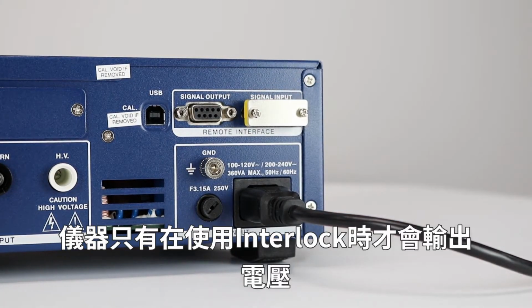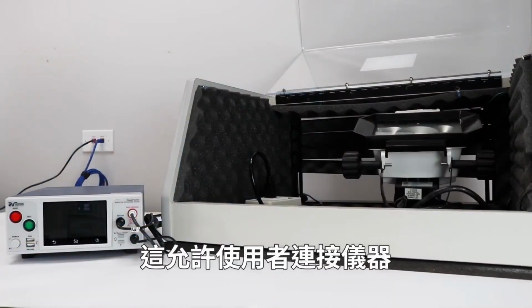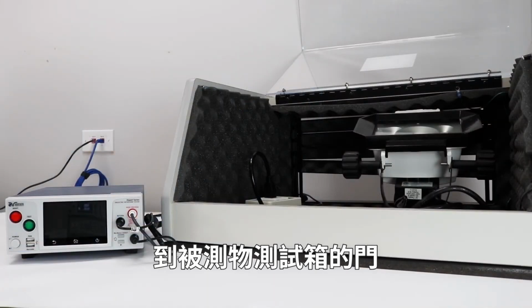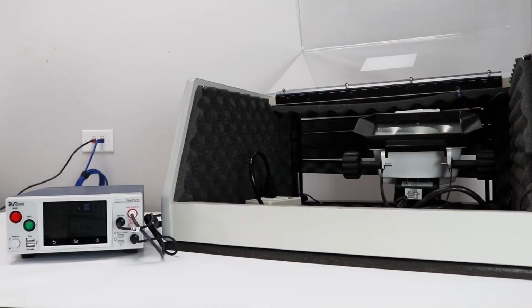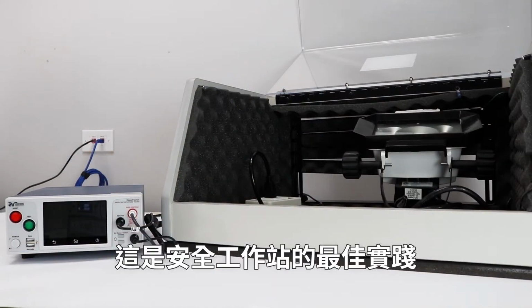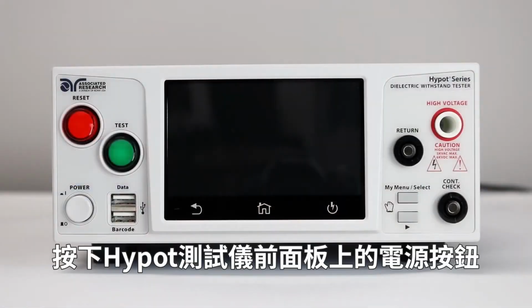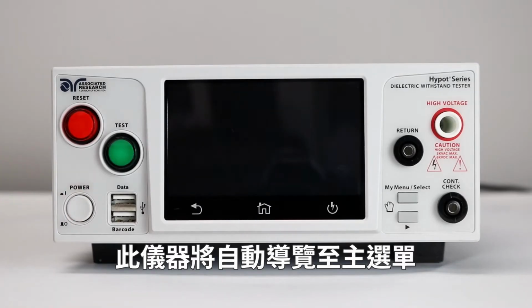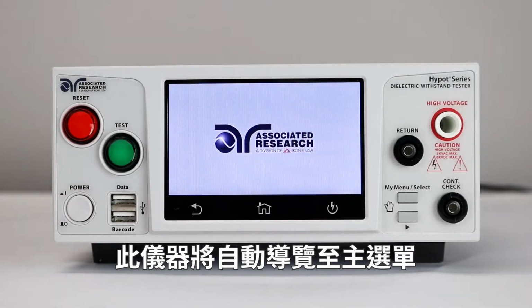The instrument will not output voltage unless you use the interlock. This allows the user to wire the instrument to the doors of a DUT enclosure. This is a safe workstation best practice. Press the power button on the front panel of the Hypot. This instrument will automatically navigate to the main menu.